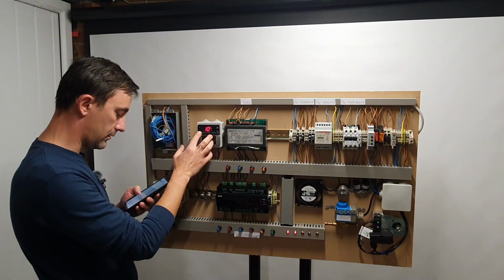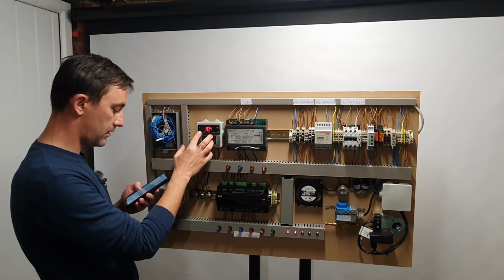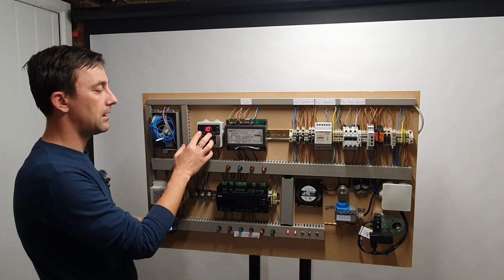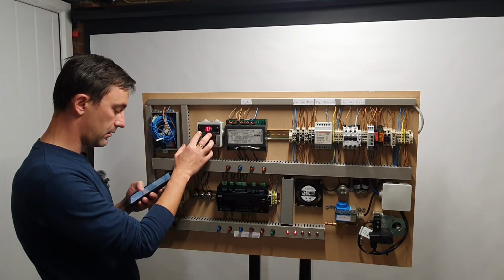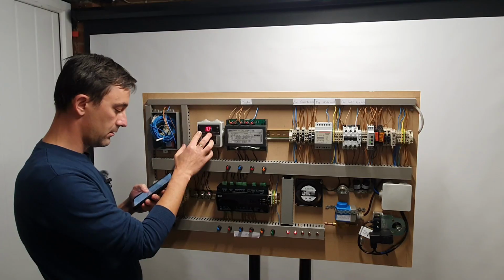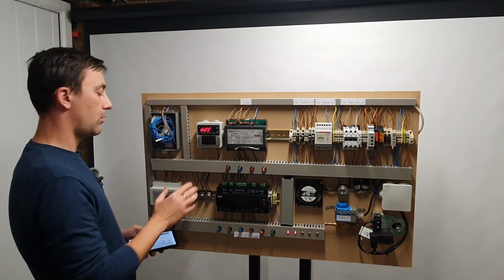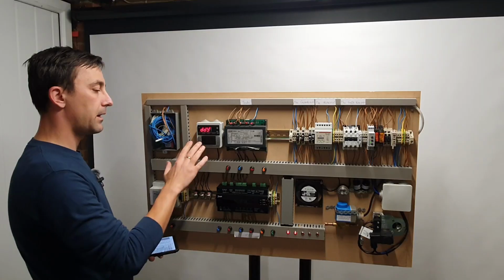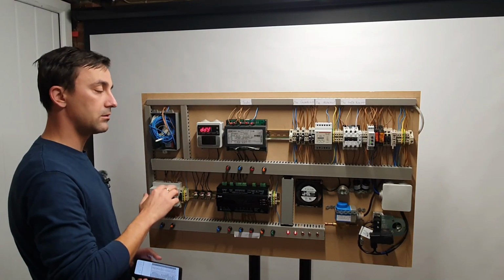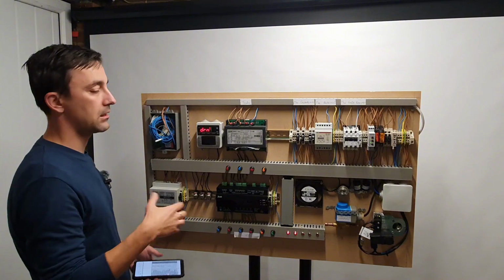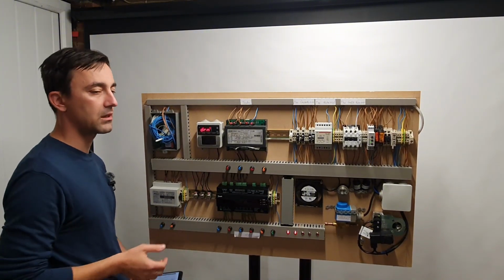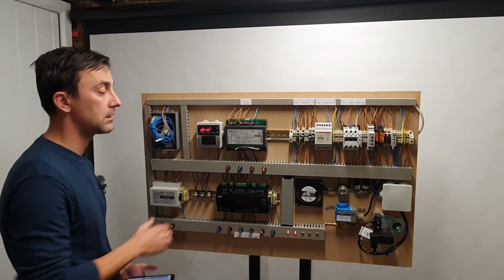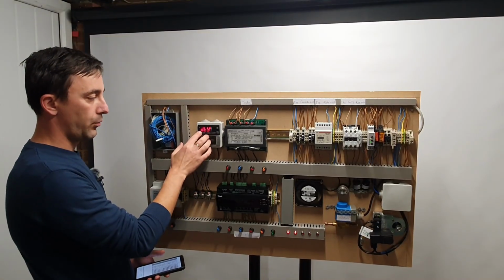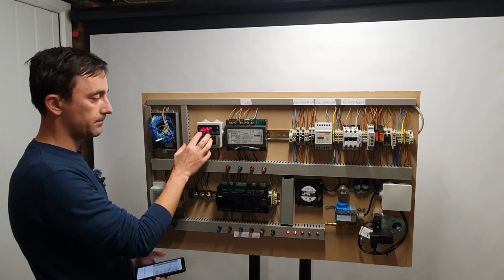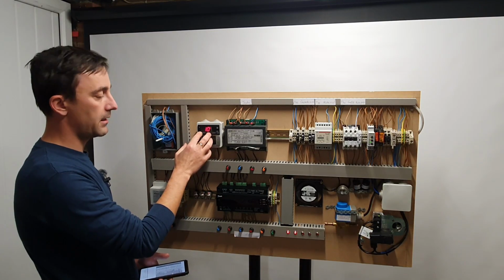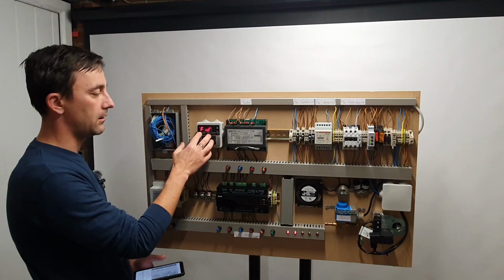DDY is defrost display control. So that's the delay. Yes. So you don't want the controller to display the temperature probe as soon as it finishes the defrost, because it can panic the customer. The air probe can read 8 degrees, 9 degrees, or 10 degrees sometimes. So you want to put a delay before the temperature is being displayed. So 10 minutes, I think that's okay.